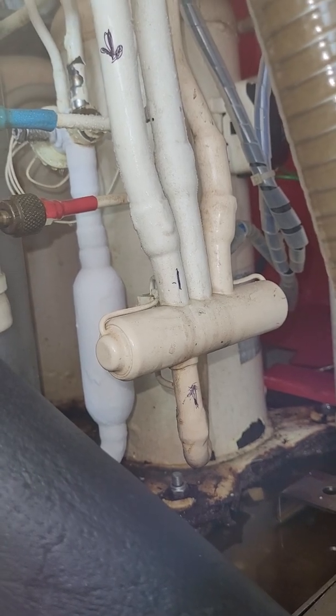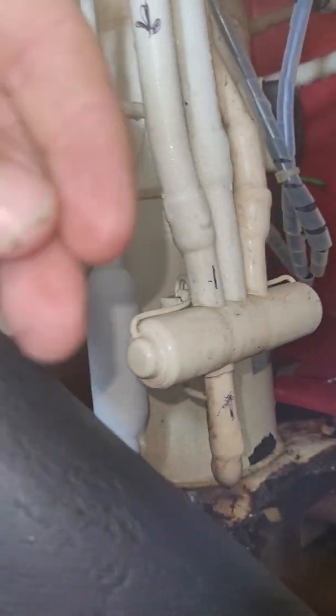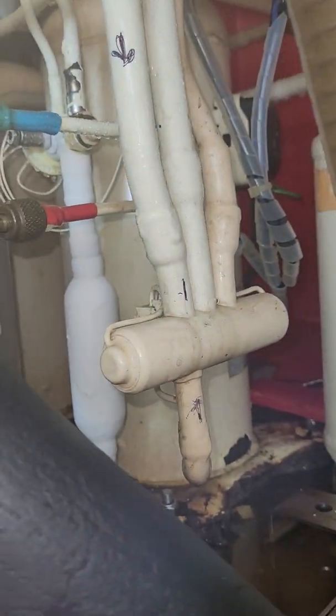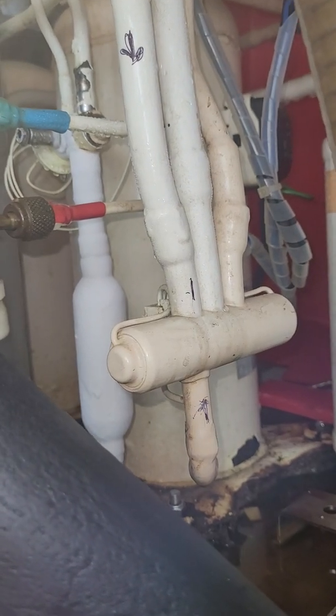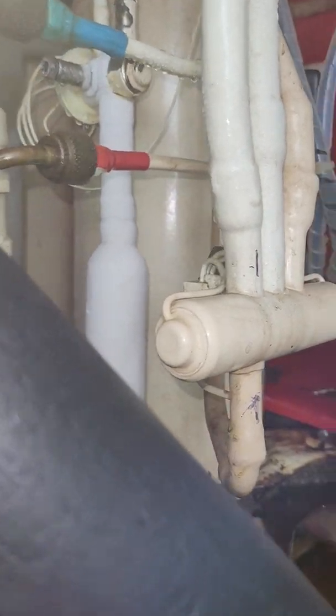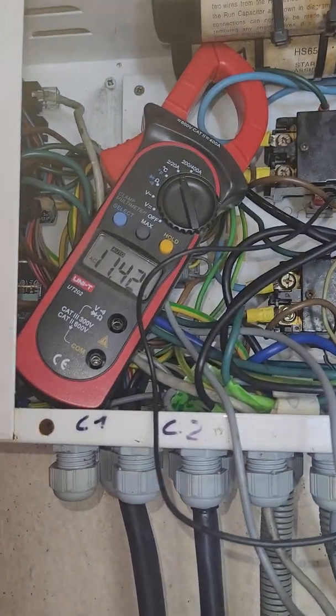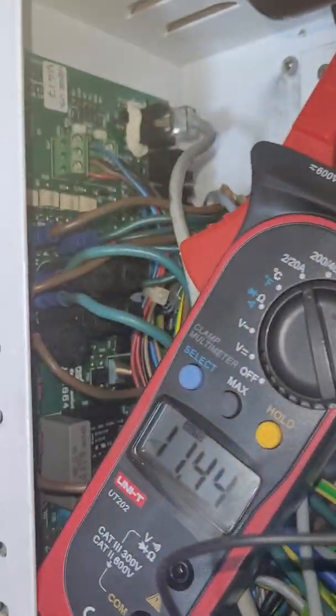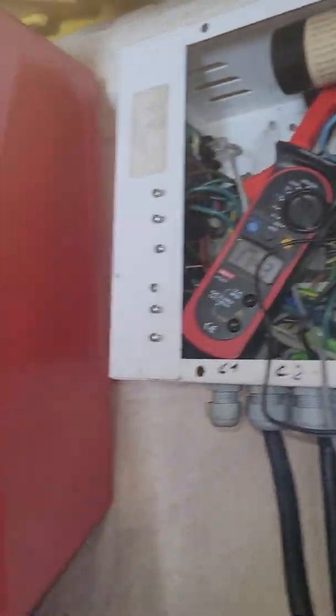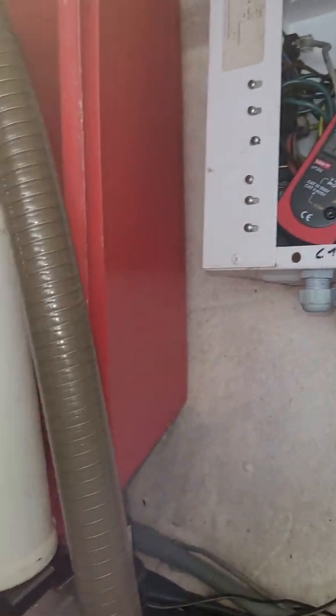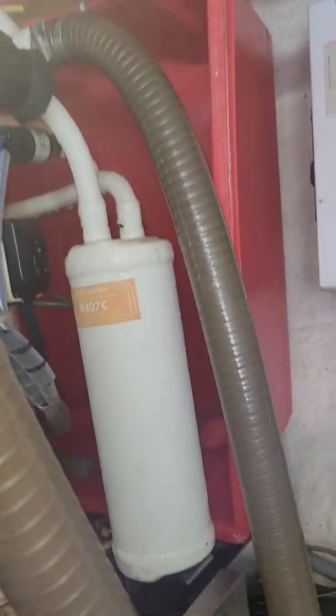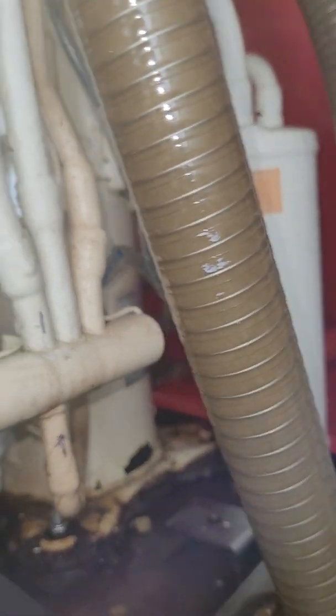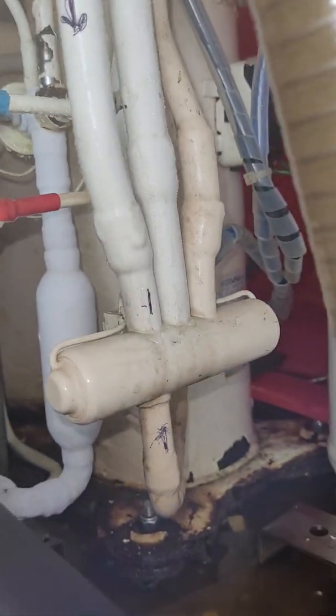And in this case, we did that. I put a little oil out. You can see it's a little oily, and it doesn't smell burned at all. So the compressor, I don't think it is actually burned out. Also, the winding amperage has pretty much stabilized. There's the electronic controls. We bridged those to make sure, there's a variety of sensors on the system, to make sure they're not messing with our diagnosis. So we're running this in a purely mechanical way.